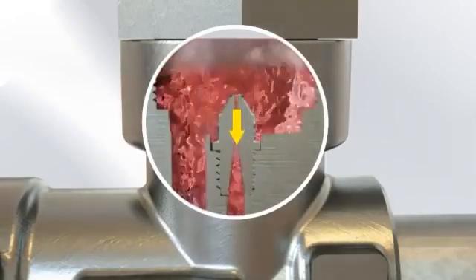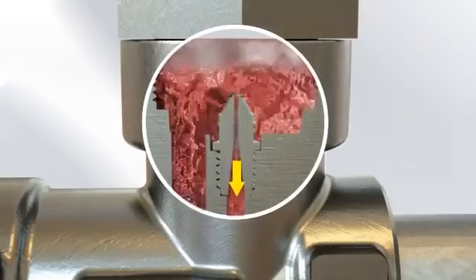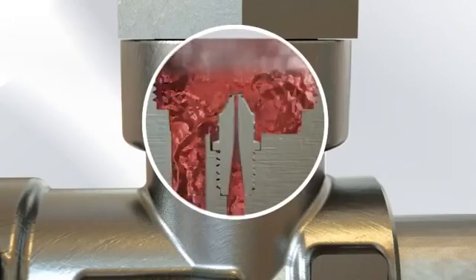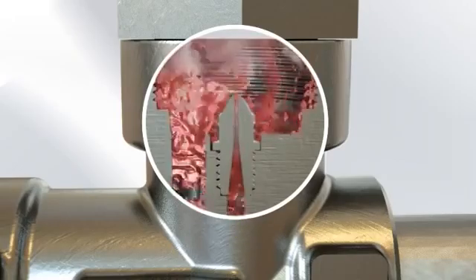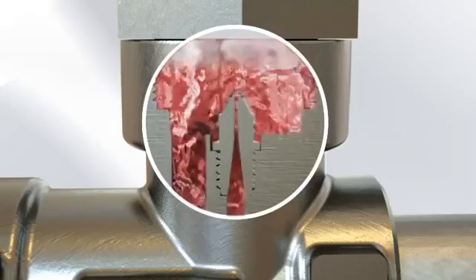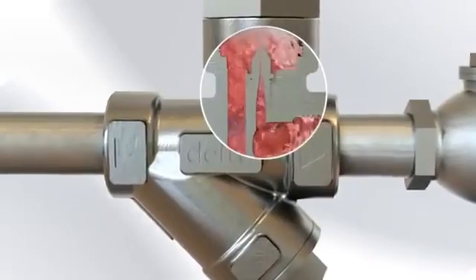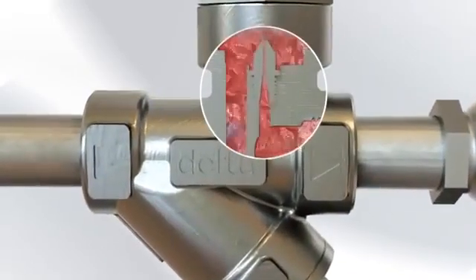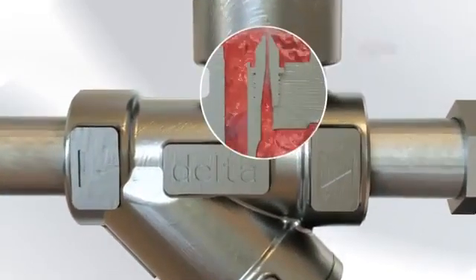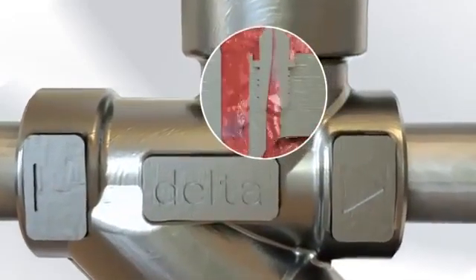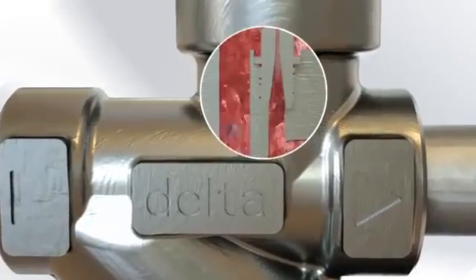This flashing creates a back pressure zone in the mouth of the Venturi. Because condensate is 1,000 times denser than steam, it is able to push through this back pressure zone while restricting the steam. As the pressure and load in the steam system vary, so too does the percentage of flash steam being created at the mouth of the Venturi in the Delta Steam Trap, which in turn allows the back pressure at the Venturi to vary accordingly.